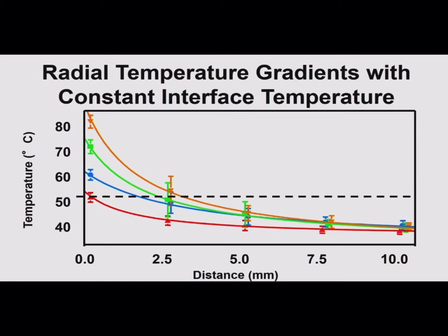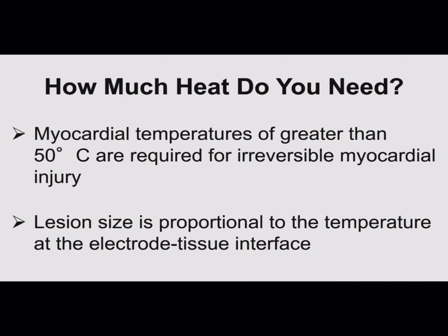Keep in mind that you're not measuring tissue temperature, and with most catheters you're not really measuring the electrode temperature — the thermistor is typically proximal to the electrode, so it underestimates the tissue temperature. That's why you won't choose 90 or 100 degrees; you'll generally choose 60 or 70 because you don't want to overheat the tissue. To emphasize: myocardial temperatures greater than 50 degrees are required for irreversible injury, and lesion size is proportional to the temperature at the electrode-tissue interface.